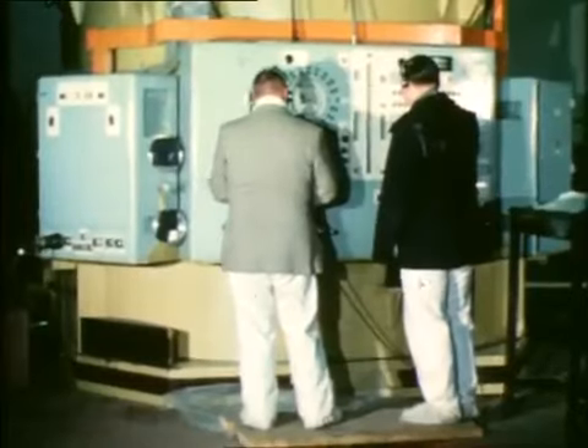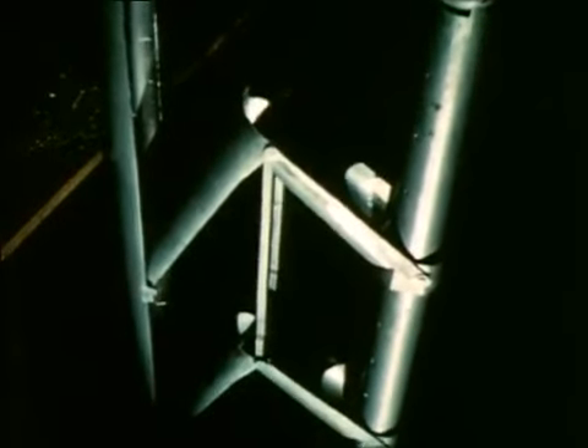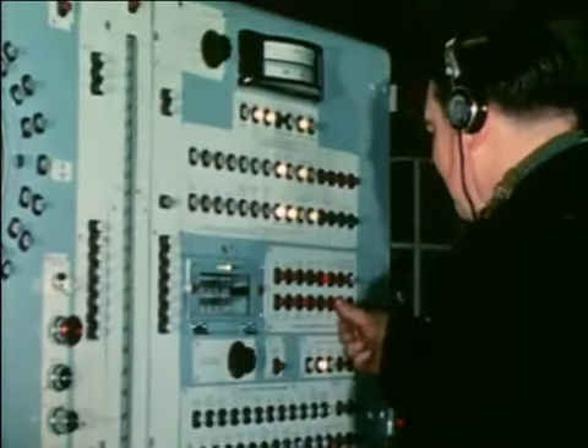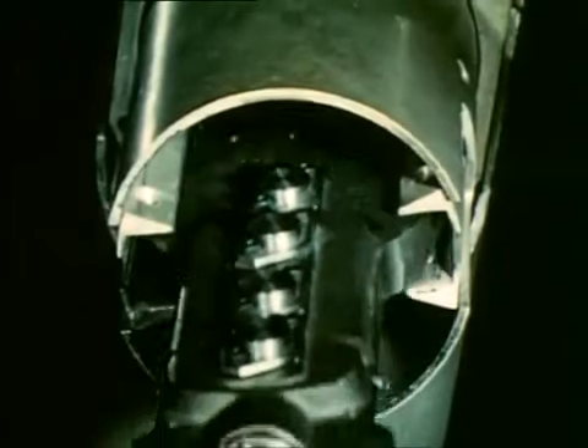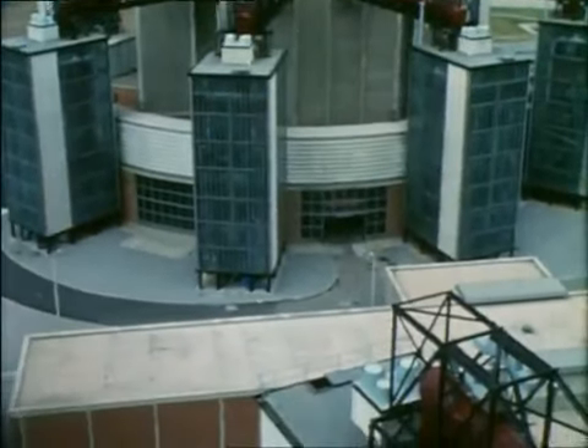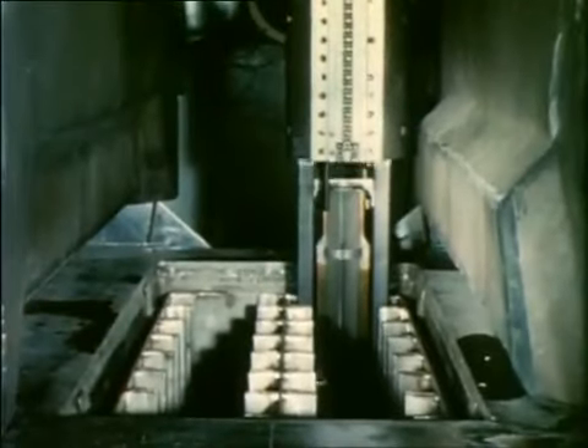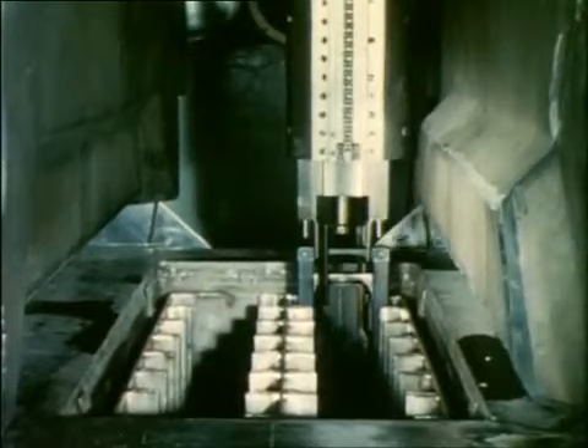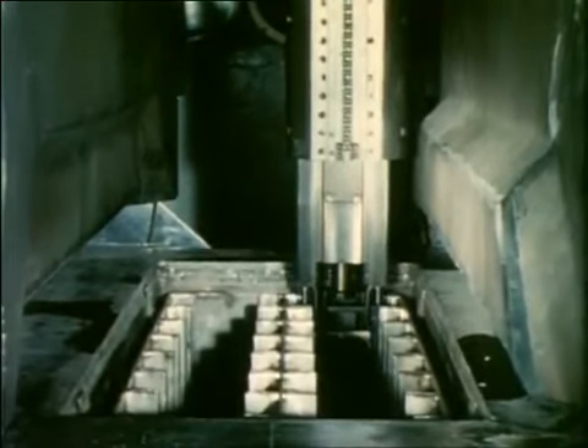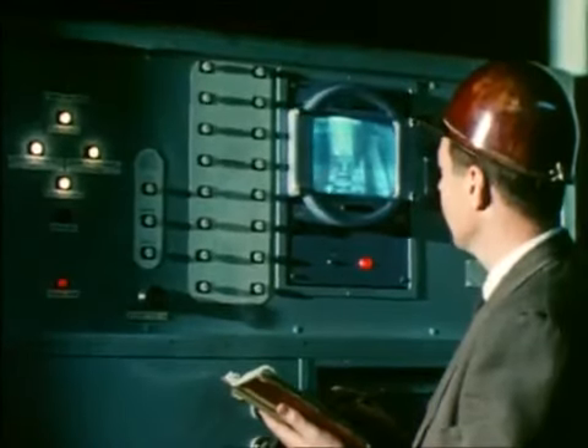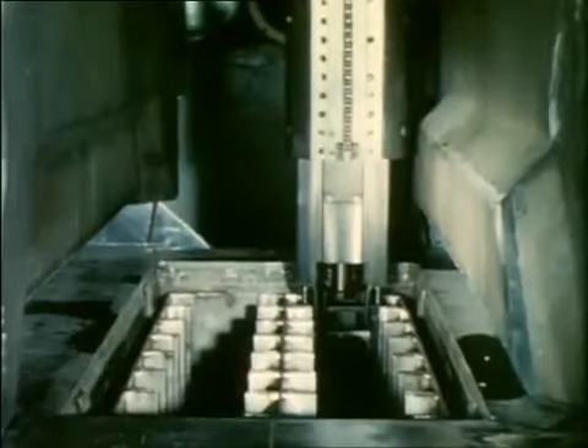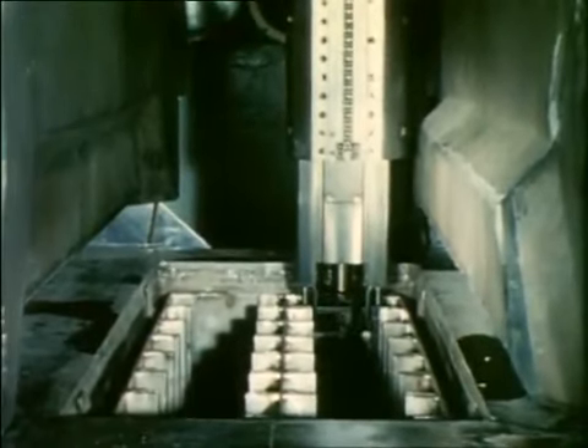The fuel chute enables the fuel elements to be lowered into or removed from the graphite core. After it's removed from the core, the spent fuel is delivered down the discharge shaft to the cooling pond 100 feet below. At the bottom of the shaft, the fuel elements are lowered by remote control into a lead-lined flask. Progress is watched by television. The machines they're testing now will take over when the reactor is on load.